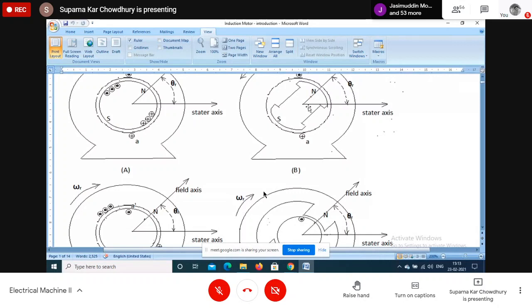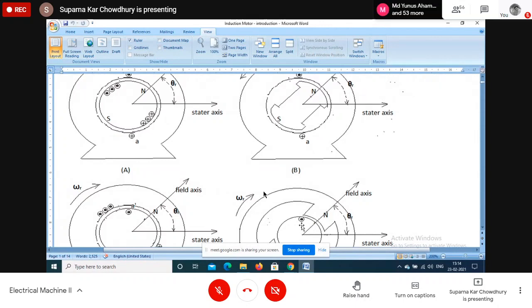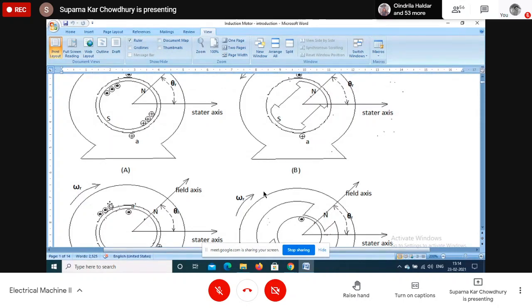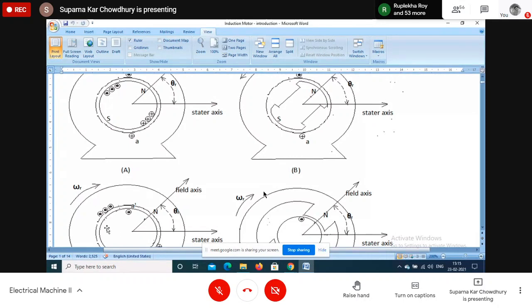Briefly, when we put the armature on the rotor, the coil is subjected to mechanical vibration and centrifugal stress. This mechanical stress puts some limitation on the voltage rating, because insulations subjected to mechanical vibration have reduced voltage withstand capacity. The same insulation that can resist high voltage on the stator cannot resist as much when the winding is put on the rotor. A static winding is easier to insulate and also easier to cool than a rotating winding.